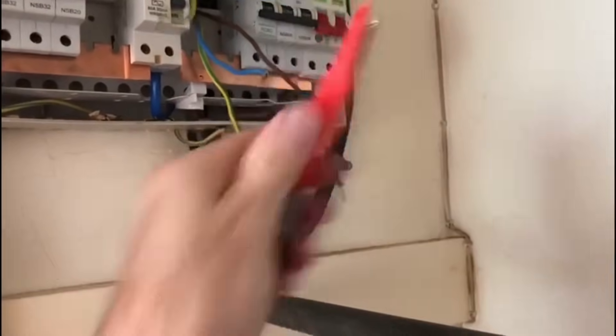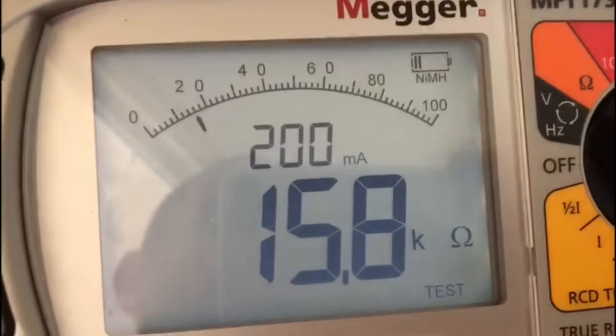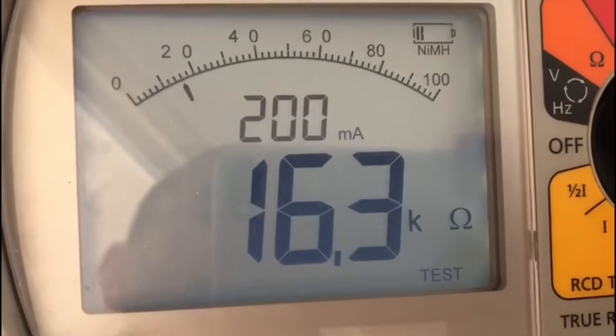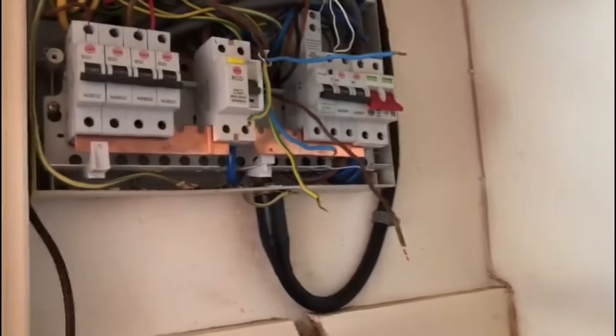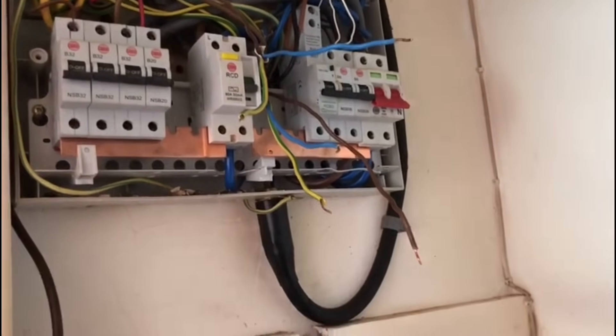Moving on to the CPC — I can hear it clicking and this time it's 15 or 16.3. I think I recorded 15.6 previously. Straight away that's showing that this isn't a ring circuit, or somewhere along the line the ring circuit has been broken.